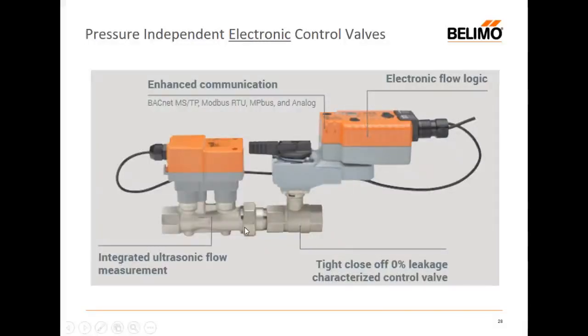Well, here's one, an ultrasonic flow meter communicating constantly with the actuator to tell it the real-time flow. And the benefits, of course, are that in this particular model we've characterized the control. So we've got class A shutoff, and because it's characterized, we've got an equal percentage characteristic. It's highly communicative, and this is the feature of electronic control valves.